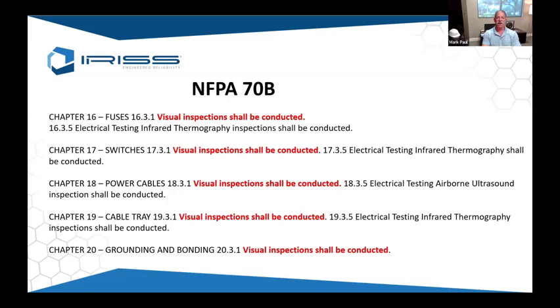But the reality is, we were just at a major new utility in Michigan about a month and a half ago. We were called in because their insurance provider said, we need to see documentation that you're following NFPA 70 requirements. They were scrambling and actually hired a reliability engineer, who said we need IRISS windows here so we can do inspections. Then we discussed thermochromics, the advantage of not only doing a visual and thermography, but now having a system doing 24/7 continuous monitoring.